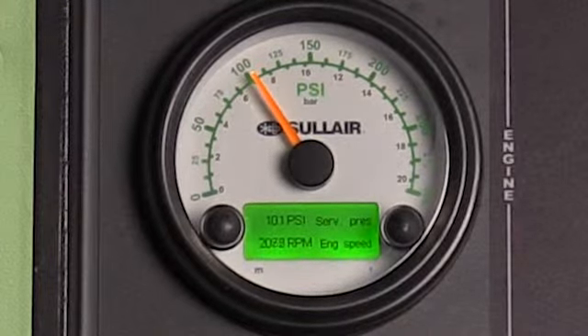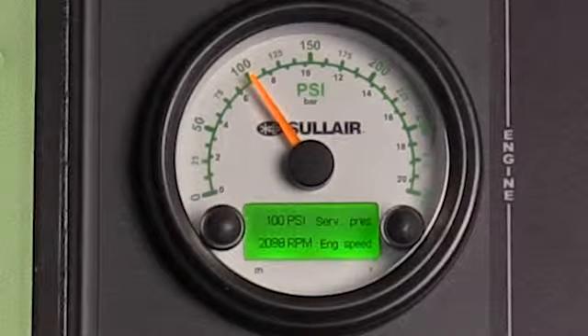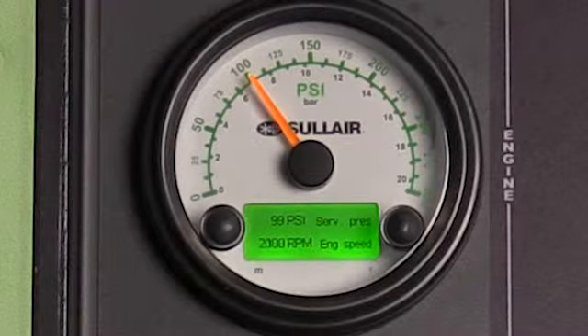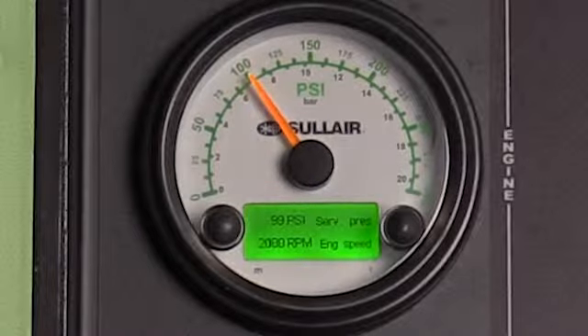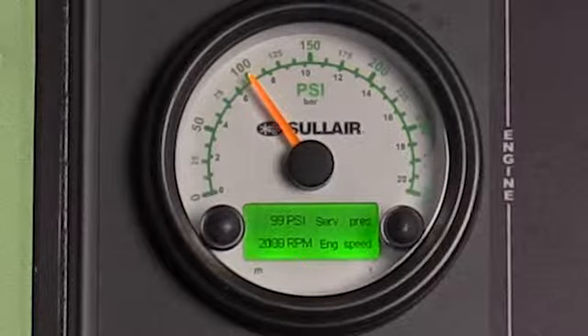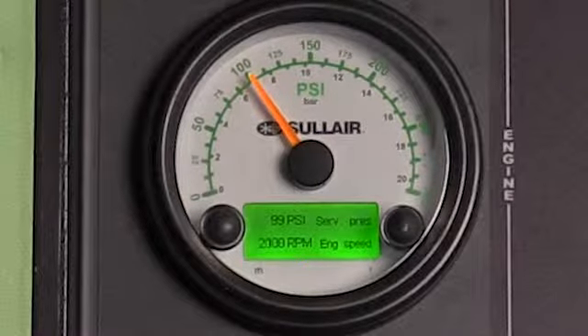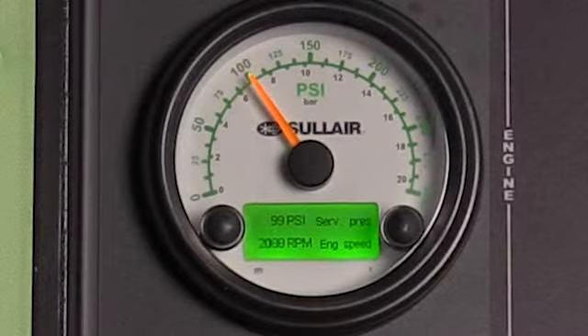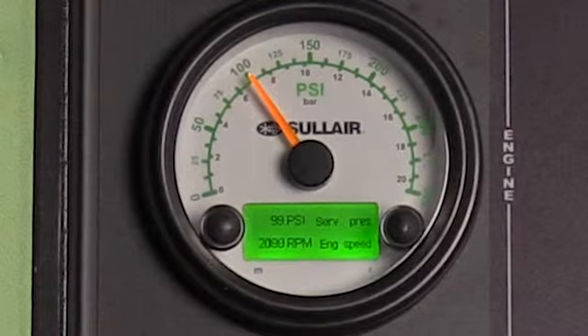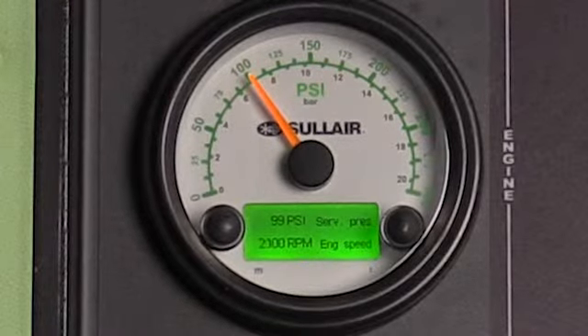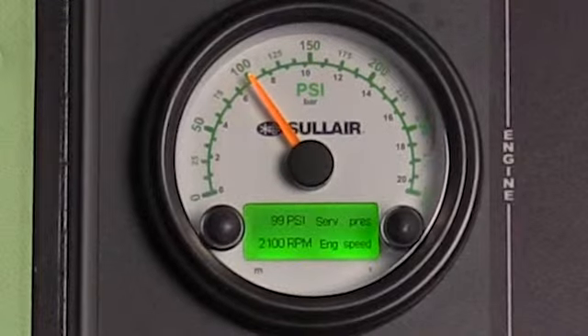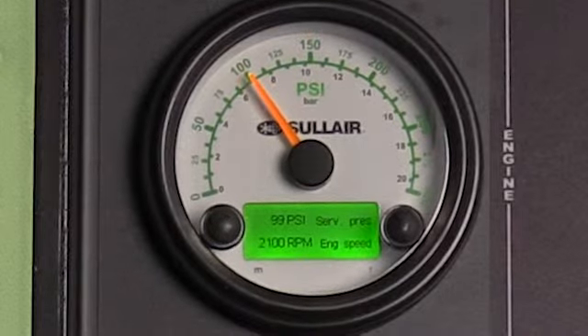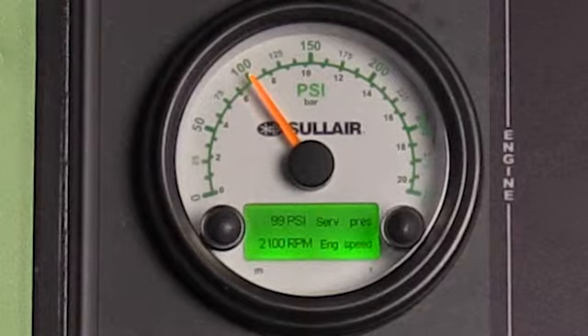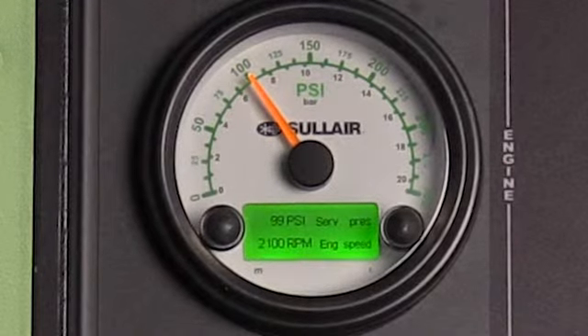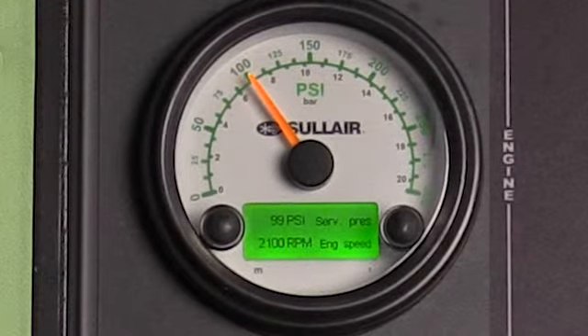What we're simulating here is the customer's demand meeting the full capacity capabilities of the compressor. The important point here is the combined total of capacity requirements of all the operated equipment does not exceed the compressor's total capacity rating. Simulated here is the loaded state. The high demand on the compressor has caused the inlet to open all the way and the engine to run at max RPM. As long as the demand does not exceed the compressor's rated capacity, then a rated pressure should be maintained.